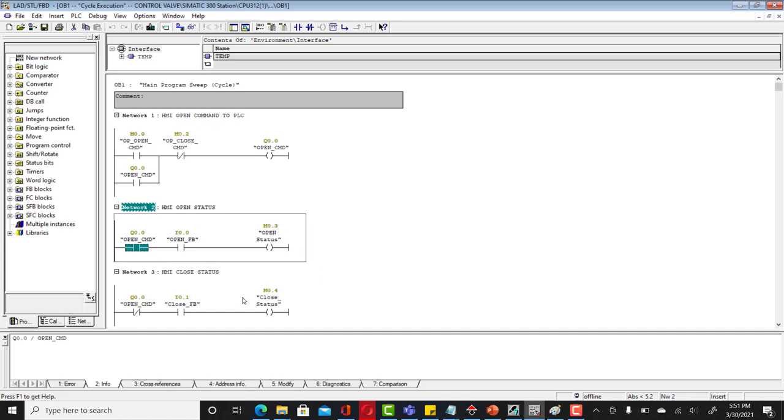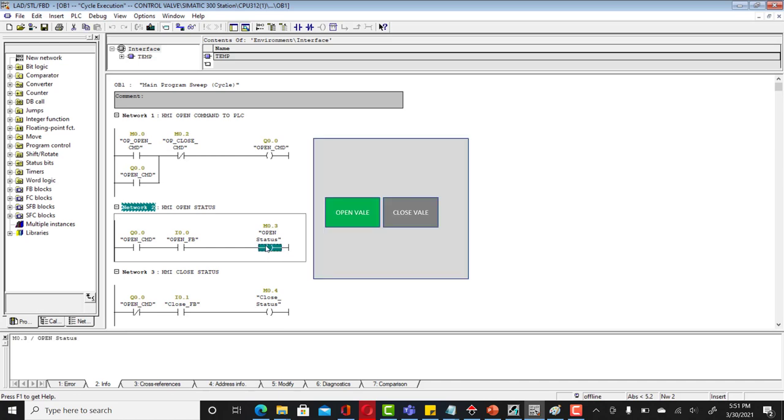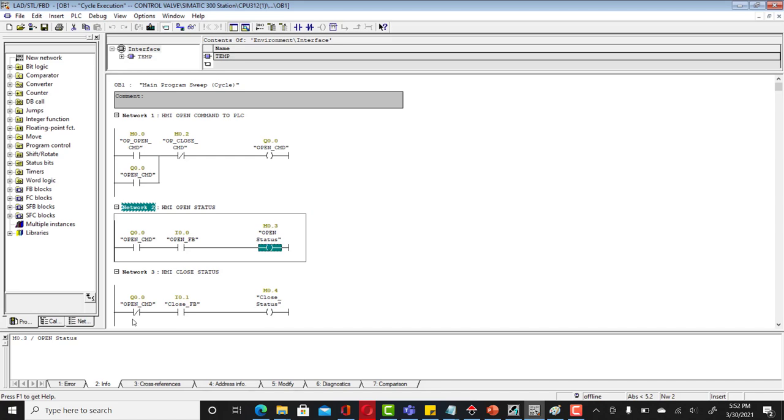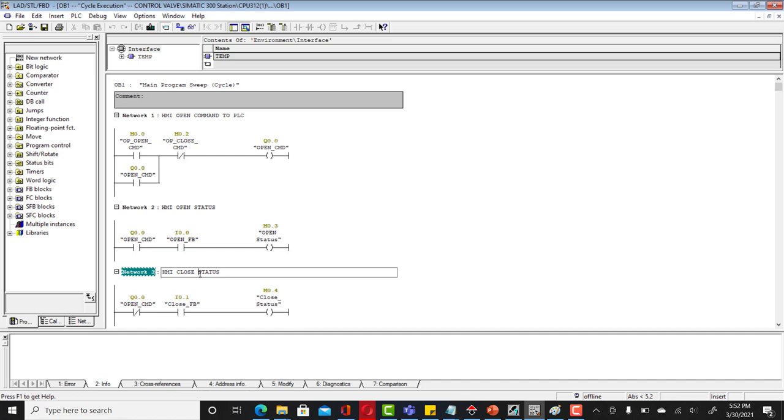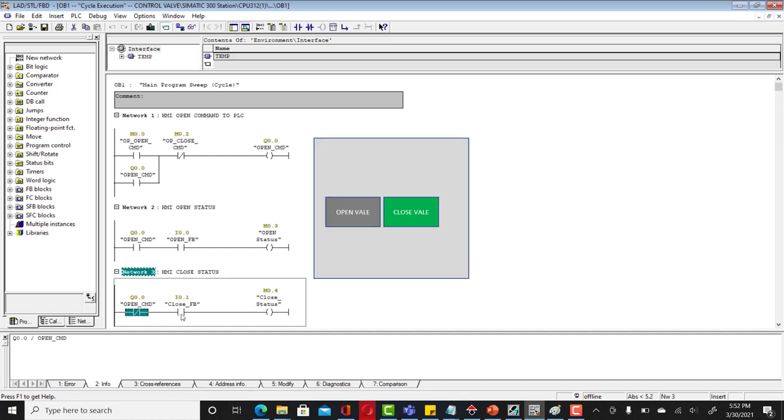This is your status signal HMI open status. If you got open command and there is open feedback, then you got open status that your valve is actually in open state and that is going to turn on the green which you can see on the screen. This is for HMI close status. If you got no open command and you got close feedback, in that case your HMI is in a close state.